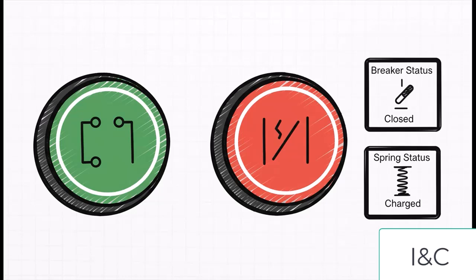Next up, you've got your hands-on controls. Super simple, super reliable push buttons. You've got a green one to close the circuit, a red one to open it. Right next to them are these mechanical indicators that give you an at-a-glance status update. Is the breaker open or closed? Is that big spring inside charged up or discharged? It's simple, it's effective, and it's actually required by safety standards.